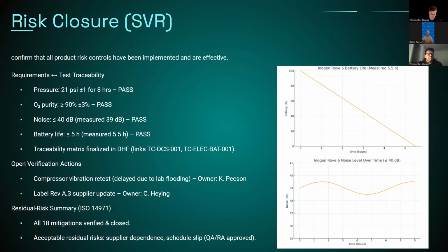For the SVR risk closure portion, our objective was to confirm that the Inogen Rove 6 meets all design input requirements before we transfer to manufacturing and finalize regulatory submission. All the critical performance requirements passed verification. We do have two open actions: the compressor vibration retest, which was delayed due to the lab flooding, and the label Rev A3 supplier update. Owners are assigned, and these items are being tracked through change control.